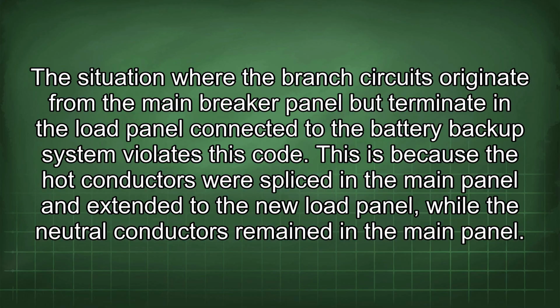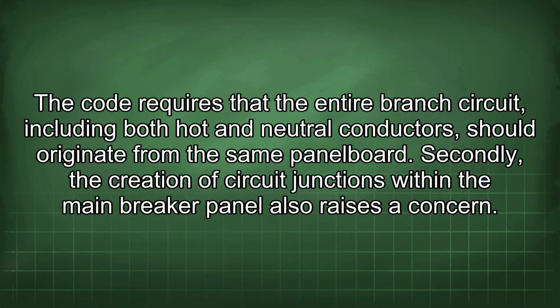This is because the hot conductors were spliced in the main panel and extended to the new load panel, while the neutral conductors remained in the main panel. The code requires that the entire branch circuit, including both hot and neutral conductors, should originate from the same panel board. Secondly, the creation of circuit junctions within the main breaker panel also raises a concern.